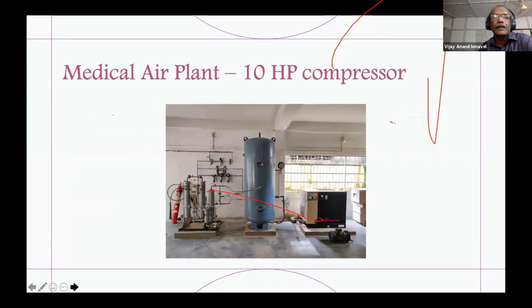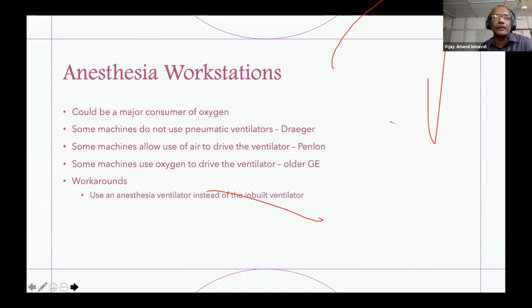I just want to go quickly through the anesthesia workstations. The Draeger workstations don't require oxygen at all for running the ventilator because it uses an electrical ventilator. Penlon allows use of air, and the older GE allows oxygen. So they will consume a huge amount of oxygen.